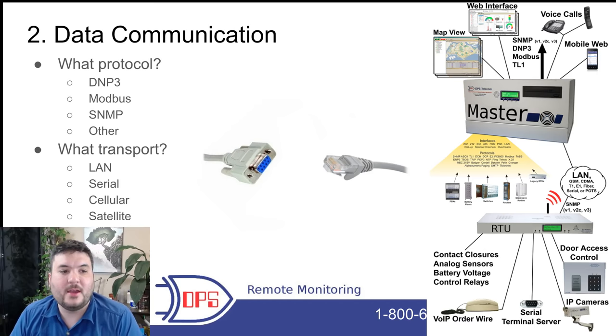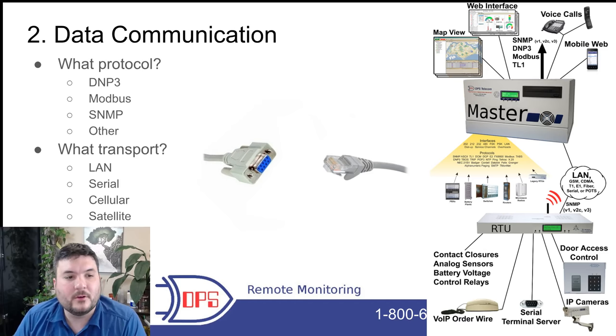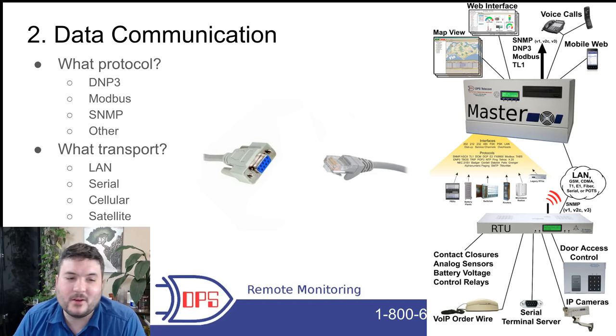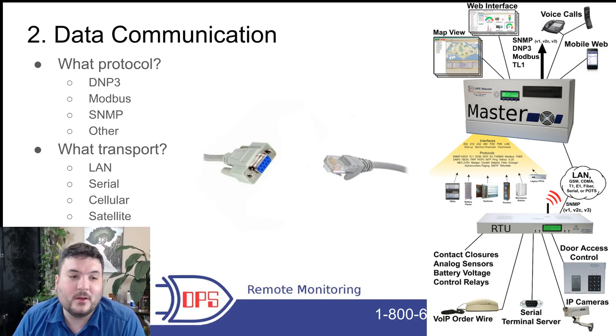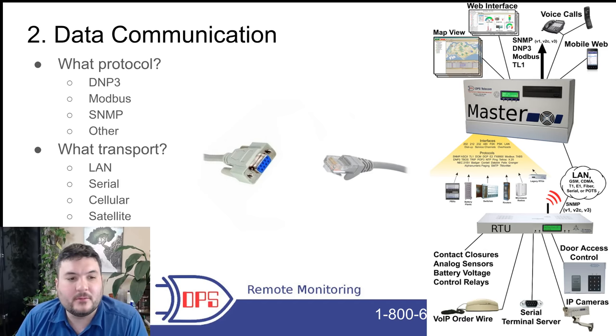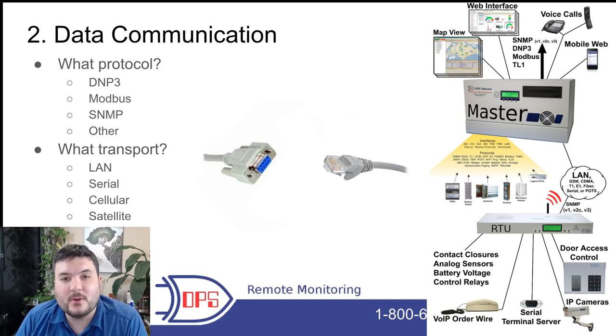Moving to data communication — two basic pieces: protocol and transport. Common protocols in the SCADA world include DNP3, Modbus, and in a telecom-type environment you might see SNMP. Some manufacturers will try to trap you with a proprietary protocol only they support, but sticking with a common standard is your best bet. Then there's transport — how are you going to send data? Is it a network link, serial, cellular modem, or even satellite? Satellite links are coming down in price and bandwidth is going up. What is the link between your remote RTUs and your central master or HMI?